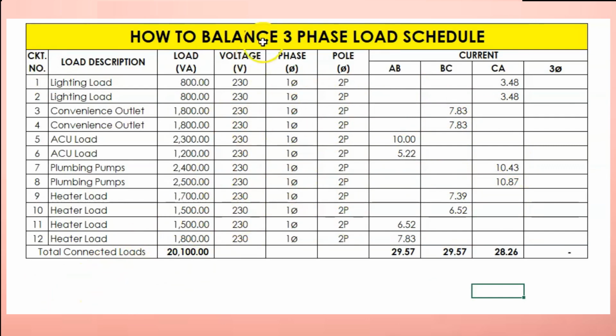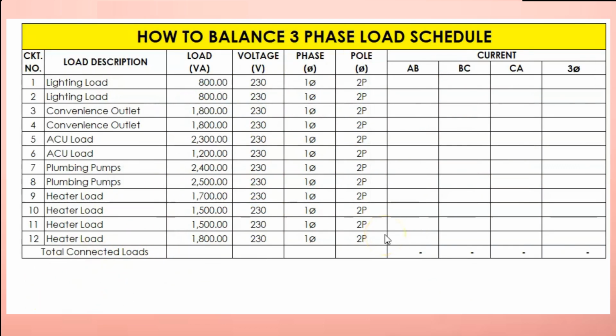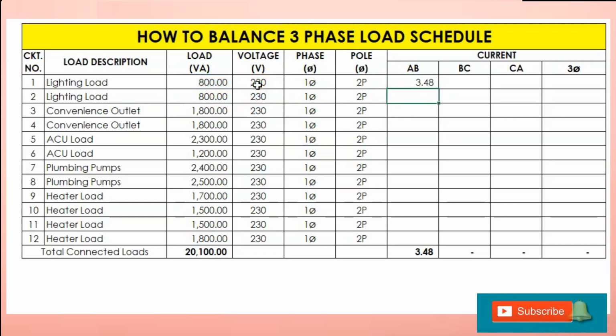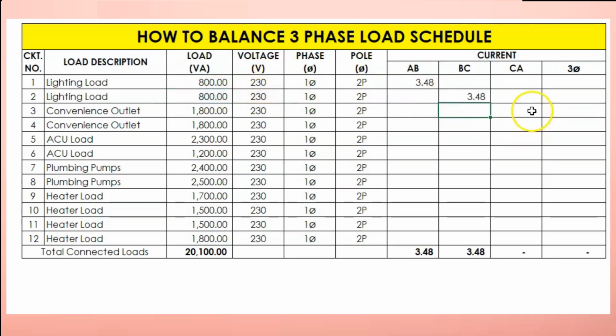Actually, it's another option, the 3-phase load schedule. Again, considering this is our load, get the total. So there's another option to balance the 3-phase load schedule. Circuit number 1, let's put on line AB. Circuit number 2, let's put on line BC. Circuit number 3, put it on line CA. Balance the rest of the circuits too.